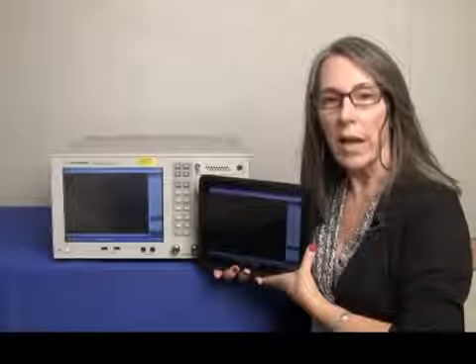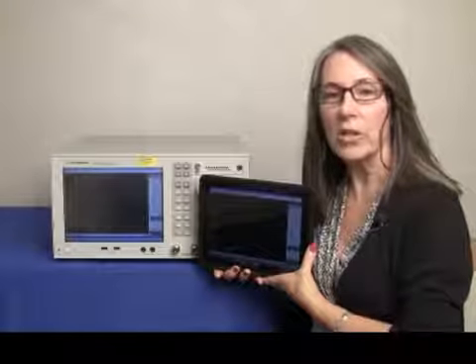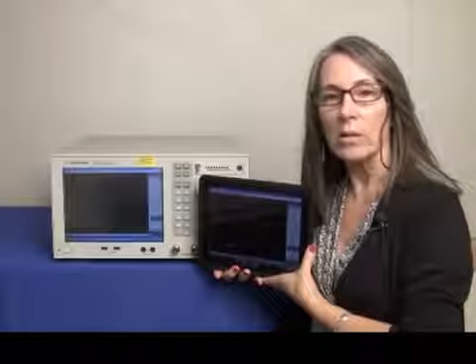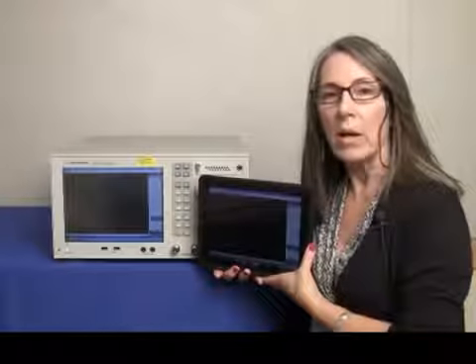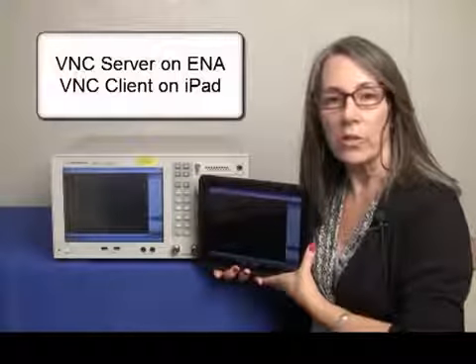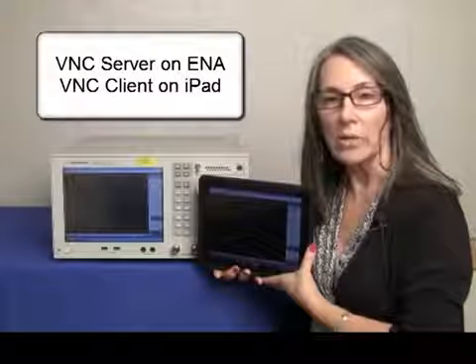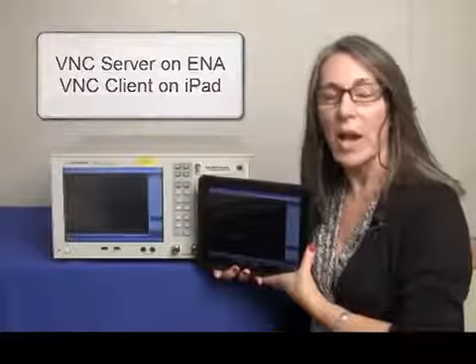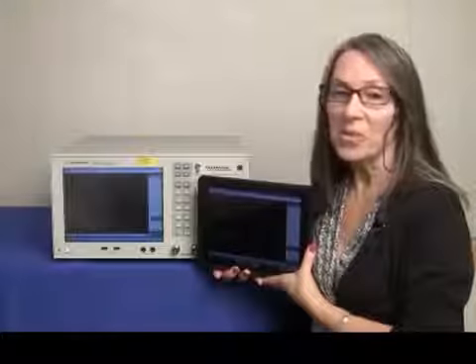Both need to be connected on the LAN, and we have a physical connection on the network analyzer and a wireless connection on the iPad. We also have the VNC server installed on the network analyzer and a VNC client installed on the iPad. I'd like to show you how to set both of those up.